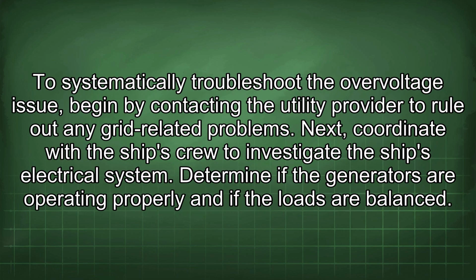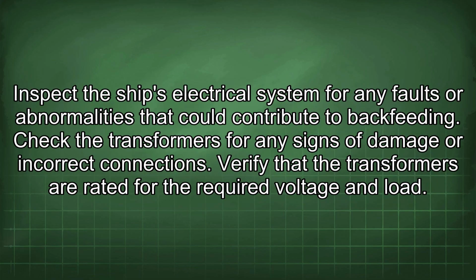To systematically troubleshoot the overvoltage issue, begin by contacting the utility provider to rule out any grid-related problems. Next, coordinate with the ship's crew to investigate the ship's electrical system. Determine if the generators are operating properly and if the loads are balanced. Inspect the ship's electrical system for any faults or abnormalities that could contribute to backfeeding. Check the transformers for any signs of damage or incorrect connections.